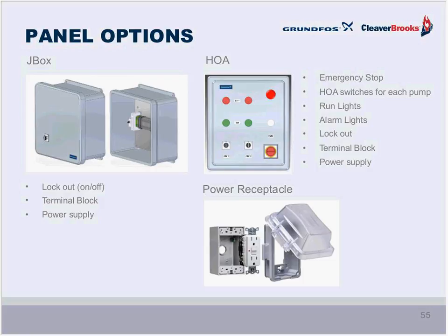Earlier, we talked about integration with building management systems. It was really brief, and with these control panels, the JBox or hand-off-auto panels are typically used in steam boiler systems where the specifications are more stringent and an increased level of automation is desired. Setting pumps to communicate with the building management systems and PLCs by laying control input cables and output cables, input to the pump and output from the pump on a terminal strip, and offer safety like lockout, emergency stop, and some status lights. Alternatively, though, an integrator may decide that there is only a need to apply power to the pumps. Control inputs and outputs can run direct to a PLC, their PLC equipment. Control panels are typically installed directly on a skidded dosing system for convenience.